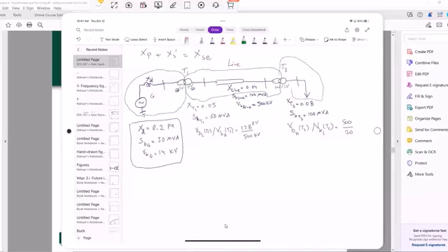So everything should be on the same base of voltage. Now for your line, as long as you are on the high voltage side of transformer number 1, up to the high voltage side of transformer number 2, this whole area has its own voltage base. And then finally, this is zone 3, or area number 3, in terms of voltage. This is the common practice that we would do for per-unitization, right? Nothing new.